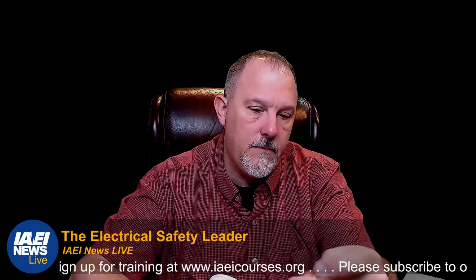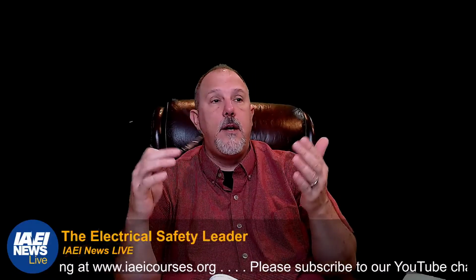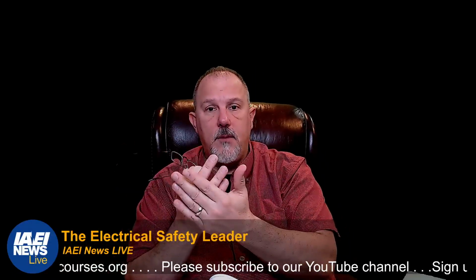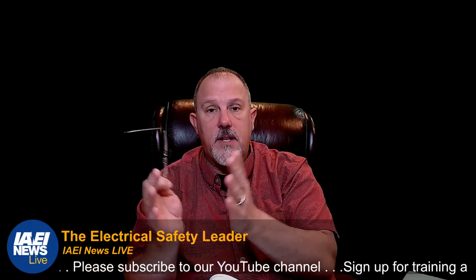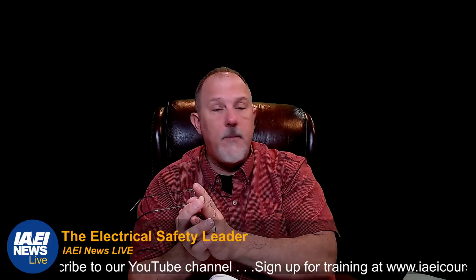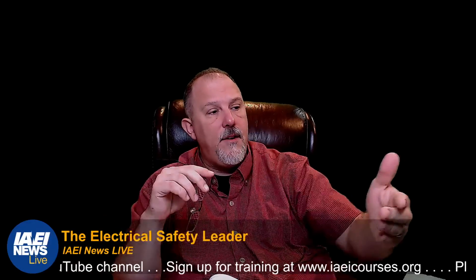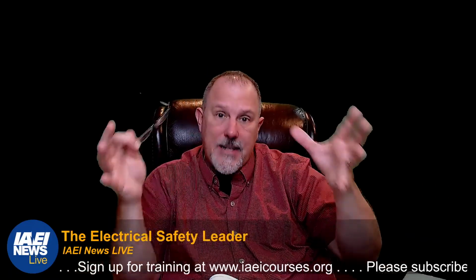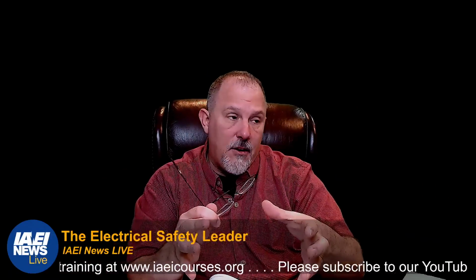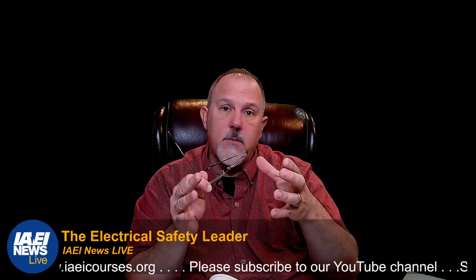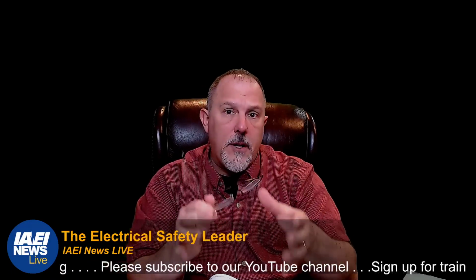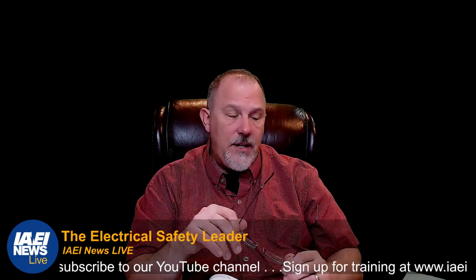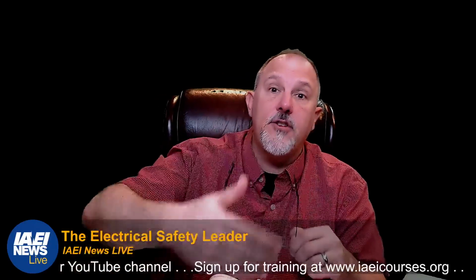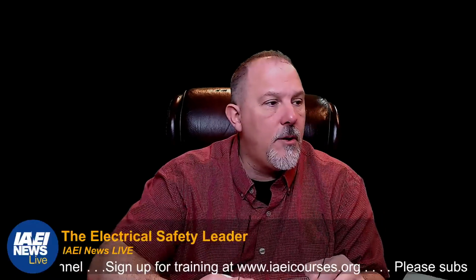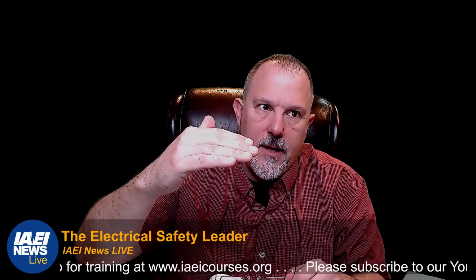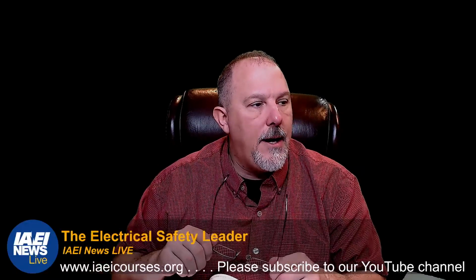If you had to replace a cover, if there were holes in the panel board that weren't covered and you had to cover them after the fact, if you had to maybe repaint the outside—any equipment malfunctions, I'd say that's the enclosure to the panel board. But on the panel board itself, if you had a breaker malfunction or a fusible switch malfunction, you had to replace circuit breakers or fuses in that panel board for whatever reason, or if you had tripping of the breakers that are part of that panel board, you'll want to document and make sure you include all of those items.